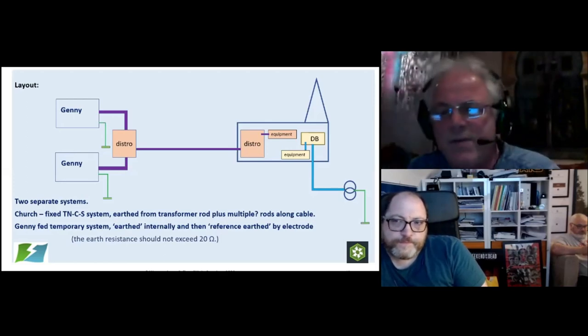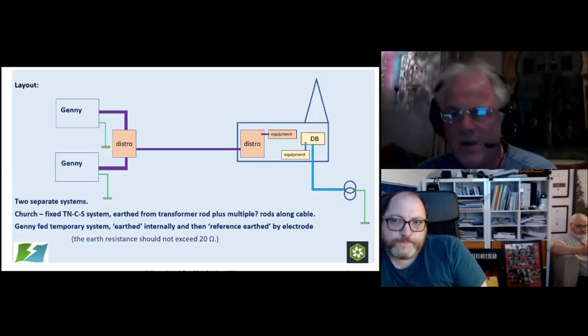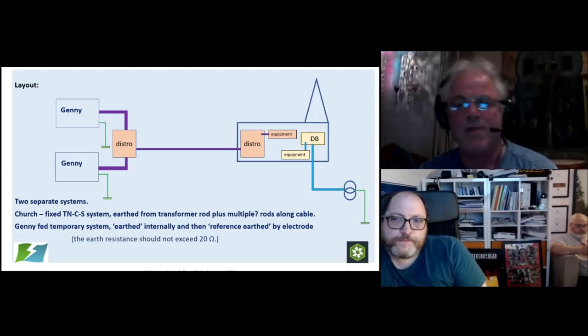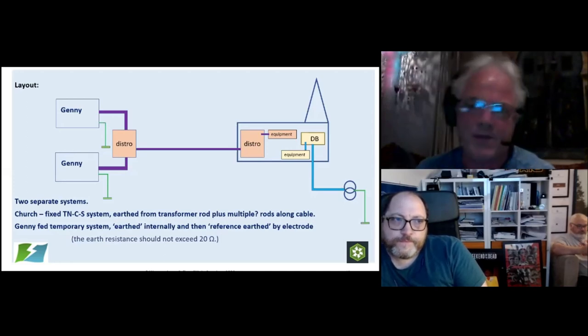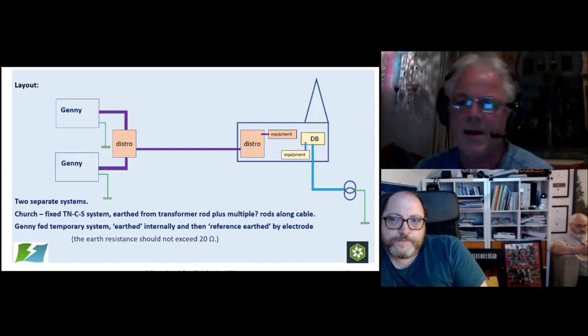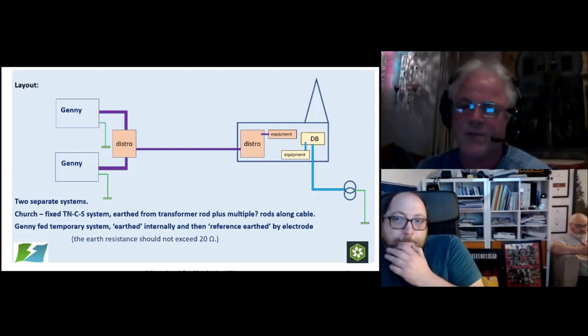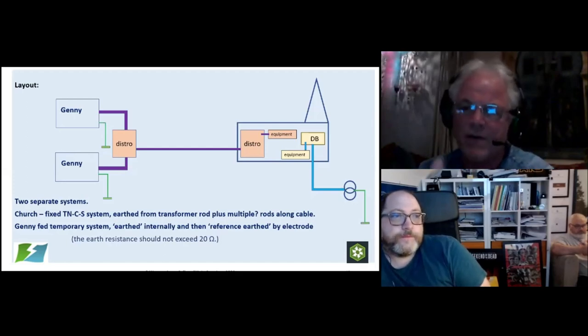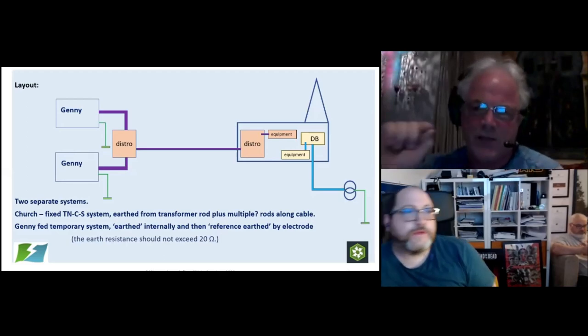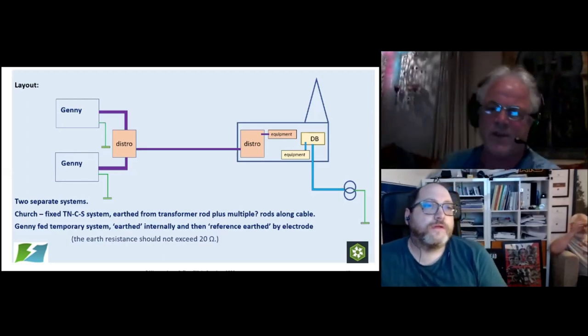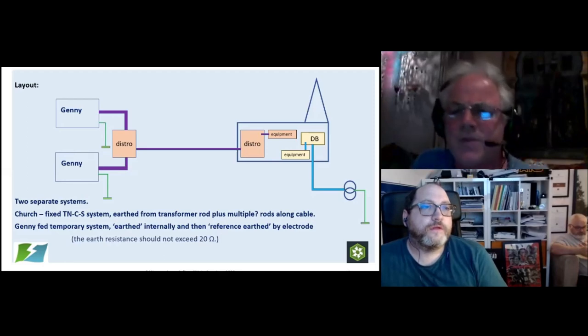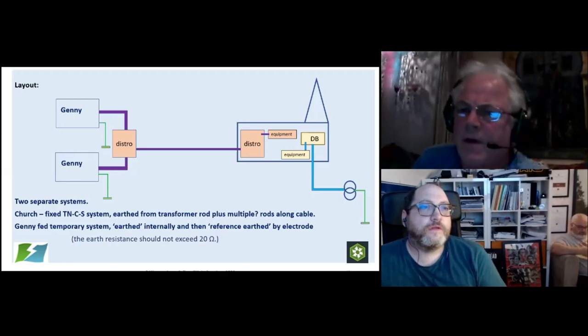Of course, that's very difficult because loads are going on and off all the time, and there will be periods of time when you may be running at over 80%. There may be periods when you're running at less than 30%, and it's very difficult on some installations to achieve a happy medium. But that's where we're aiming to be, 50, 60, 70%. So that's the thing with rating of generators.